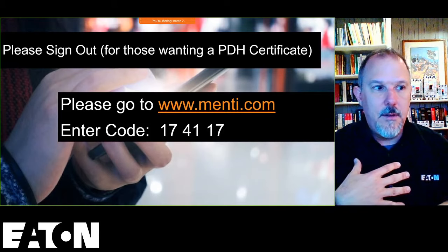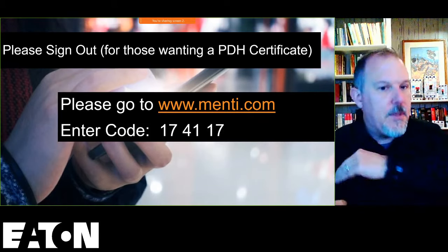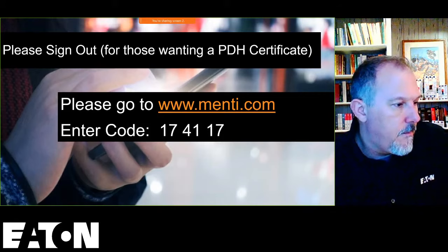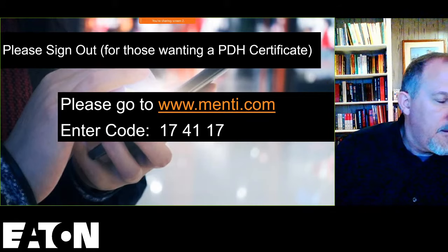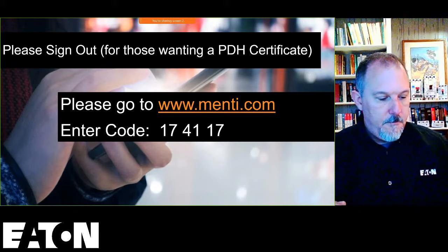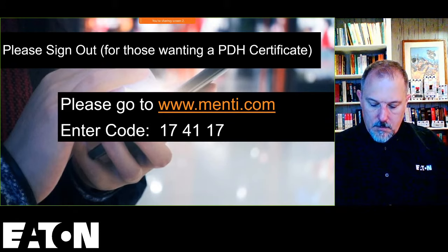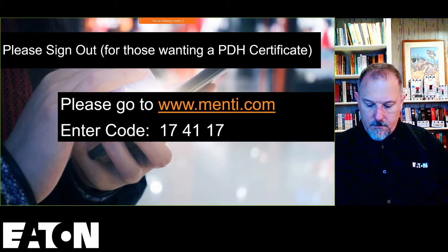Tom, can I unmute myself? One second? Please. 440.4(B) is not a requirement that the installer does. It's a requirement for the manufacturer. It says the manufacturer has to have a nameplate. They have to tell you the minimum conductor and the maximum ground fault and short circuit, and those calculations that the manufacturer is required to do are based on the required calculations of part three and part four.